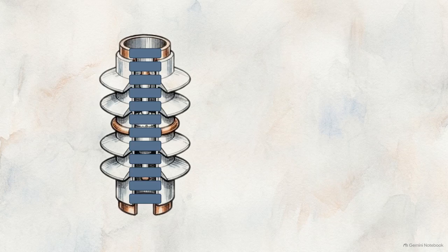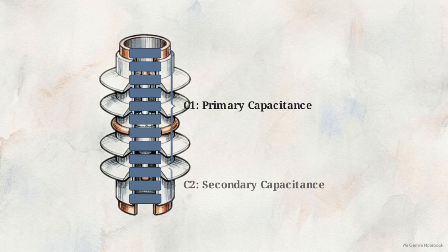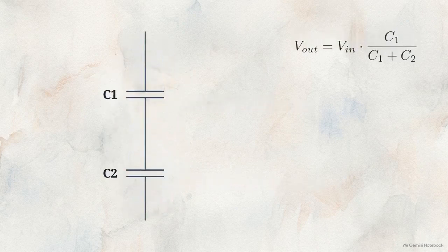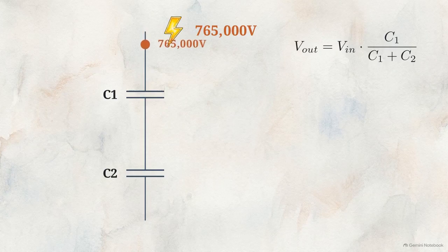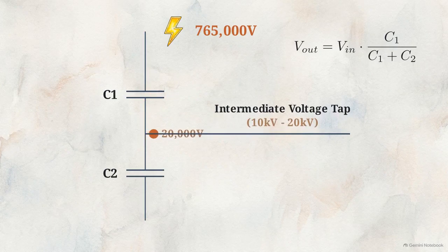Electrically, this long stack is split into two distinct groups, a primary capacitance section called C1 and a secondary capacitance section called C2. When alternating current passes through a capacitor, it encounters impedance. By placing two capacitor groups in series, they act as a pure voltage divider. The raw 765 kV grid power enters the top of the C1 stack. Because voltage drops proportionately across capacitors in series, a much smaller intermediate voltage is tapped exactly between the C1 and C2 groups.